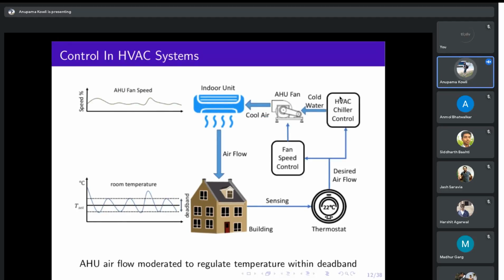On the other hand, if you have a larger HVAC, the system is a slightly more complicated system. There are more components there. What typically happens is there are two components here. This could be for anything like a big chiller plant type system or even a variable refrigerant flow type system. What you would have is a separate mechanism for cooling your air, and a separate mechanism for directing the cooled air into your building or environment where you're trying to cool, right? And so what happens is you still have a sensor, you still try to measure whether the internal conditions are within the band we want that temperature to be, and then based on that you control the speed, or you regulate the airflow into the system through a fan, and the speed of this fan is controlled to make sure that you get that desired temperature set point. And this is usually some sort of a proportional integral control mechanism that would kick in here.